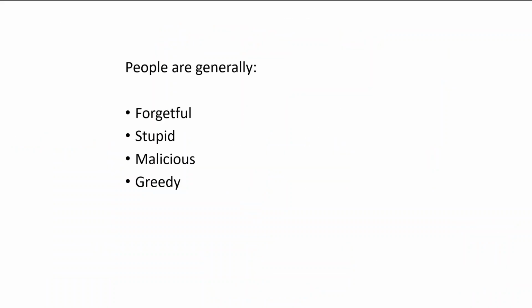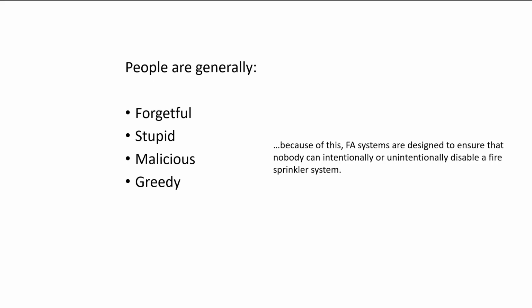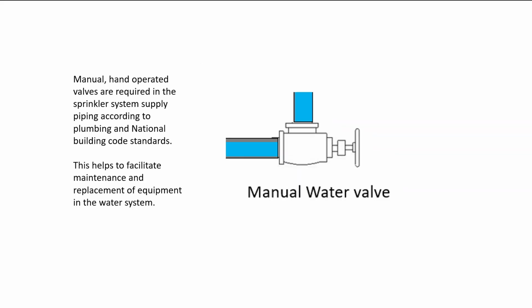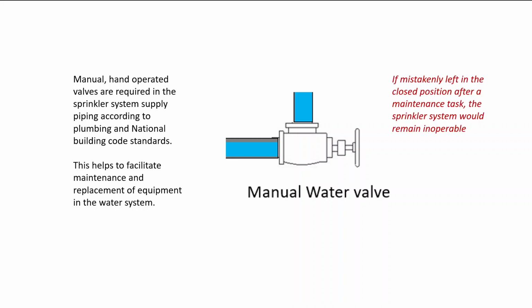Now, it's important to understand that people are generally forgetful, stupid, malicious, and greedy. Because of this, fire alarm systems are designed to ensure that nobody can intentionally or unintentionally disable a fire sprinkler system. Manual hand-operated valves are required in the sprinkler system supply piping according to Plumbing and National Building Code standards. This helps to facilitate maintenance and replacement of equipment in the water system. If mistakenly left in the closed position after a maintenance task, the sprinkler system would remain inoperable.